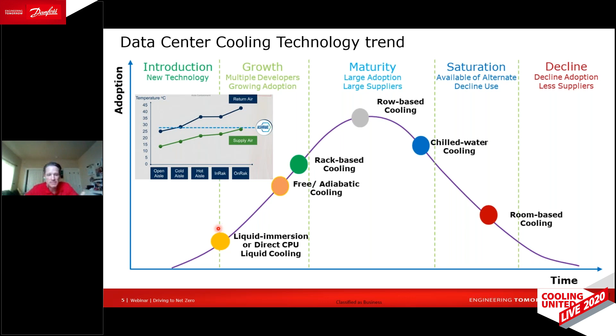And on that, specifically with the R technology, this is where I transition to talking about the Danfoss technology and specifically the Turbocor compressors, and how it fits with both trends. As you increase the cooling temperature and decrease the heat rejection temperature, the result is lower lift, or lower differential temperature. If you have equipment that can operate at those minimal differential temperatures, then you have more efficient equipment. The thing about oil-free systems, whether or not they're Danfoss-based systems or systems based on other people's technology, is that in general they can operate at those lower lift or lower differential temperatures, and therefore lower pressure ratios.